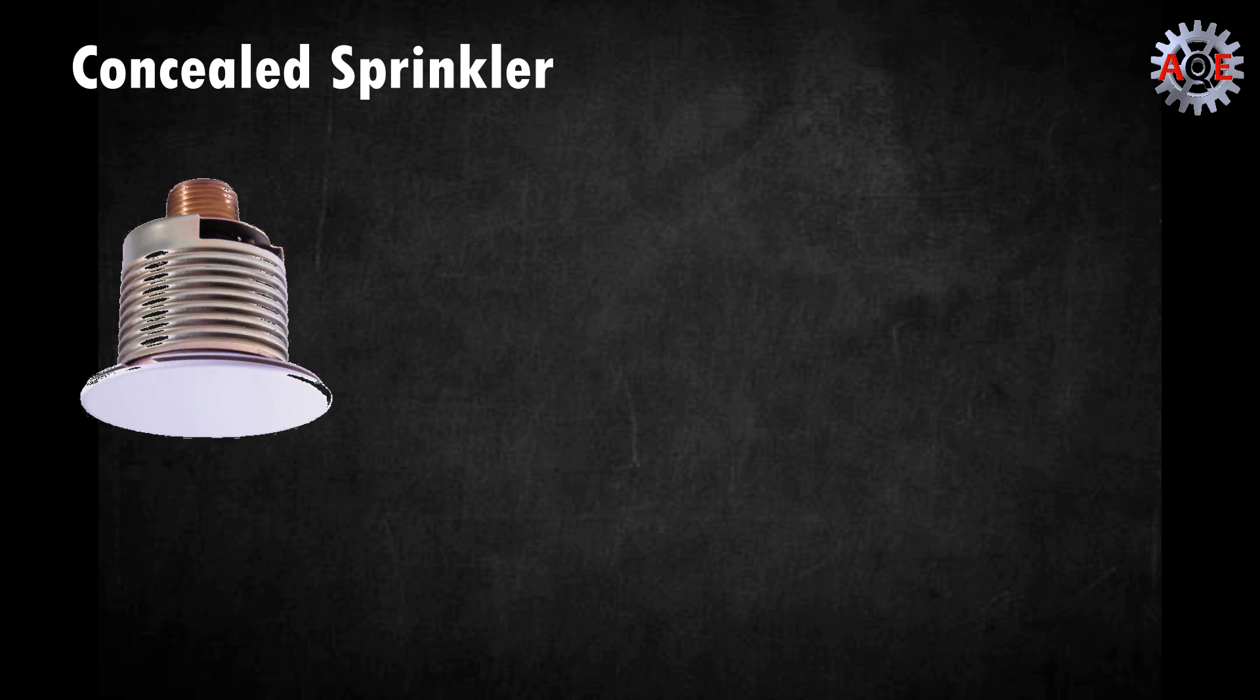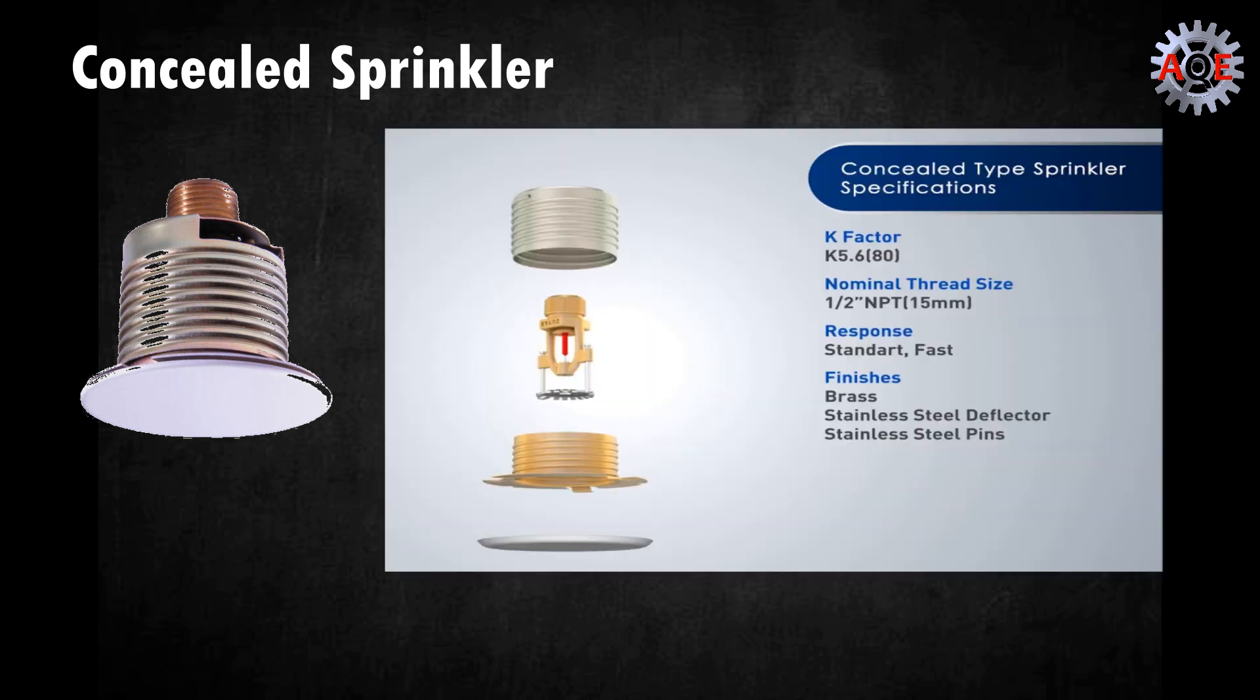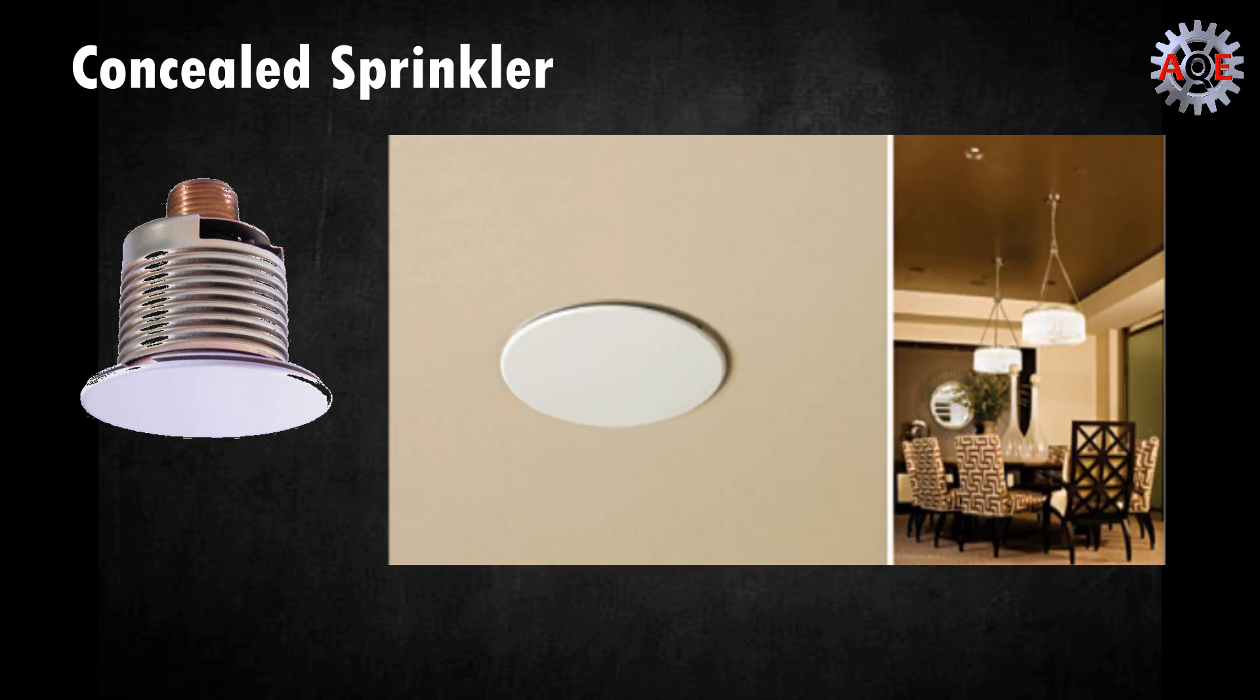A concealed fire sprinkler head is very similar to a pendant fire sprinkler head. However, the concealed head has a cover plate to help it better blend into the ceiling. The cover plate will fall off once the temperature is 20 degrees less than the fire sprinkler, which allows the sprinkler to activate once it's exposed to the heat of the fire.